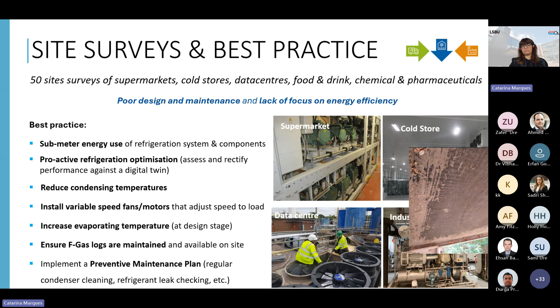In terms of improving efficiency at the design stage, one of the most important things is to increase the evaporating temperature, but this needs to be done at the design stage. We also found that F-gas logs were not always available on site - it's a legal requirement to have them, and they might exist but were not available on site. It's critical to implement a preventive maintenance plan, with better communication between end users, refrigeration contractors, technicians, and designers to make sure the system is not just running but continuously improved.